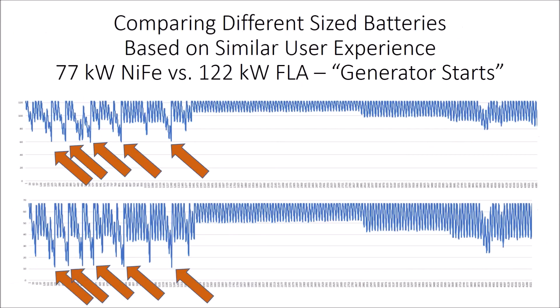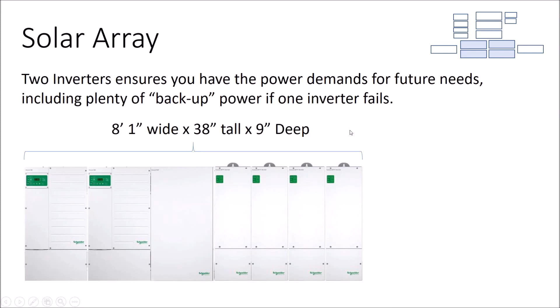Yeah, here we are on the next slide. So we need 5.5 feet for our batteries, and 8 foot 1 inch wide for our 2 inverters, our service panel, and our 4 charge controllers, to have everything look nice and neat. We were designing this system but didn't take into account that it wouldn't fit if we put it all along the same wall. So we're putting it along this wall, removing this door, and turning the corner to put the rest of the equipment there.